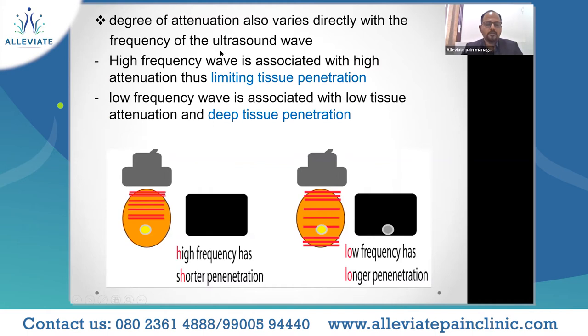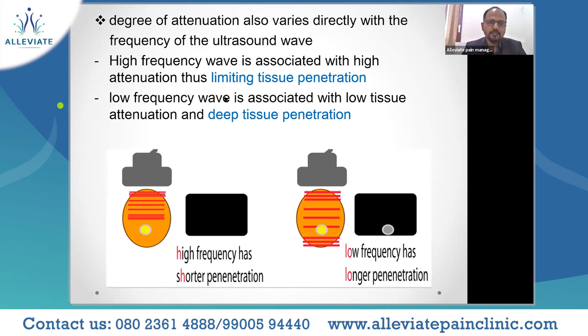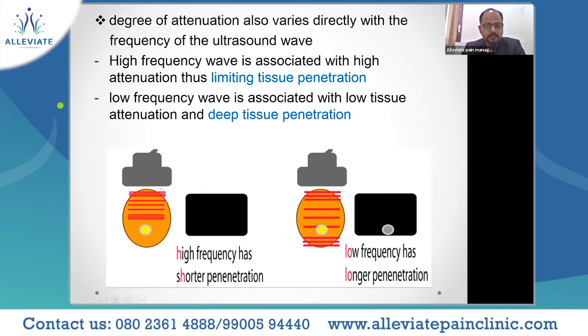The degree of attenuation also varies directly with the frequency of the ultrasound wave. Higher frequency means higher attenuation coefficient, thus limiting tissue penetration. Conversely, low frequency is associated with less tissue attenuation and less absorption, allowing penetration into deeper tissues. For example, if the target is way beyond 4 centimeters and you use a linear probe (high frequency), it will get attenuated and you won't visualize the structure. If you use a curvilinear probe (low frequency), penetration is better and you are able to visualize it.